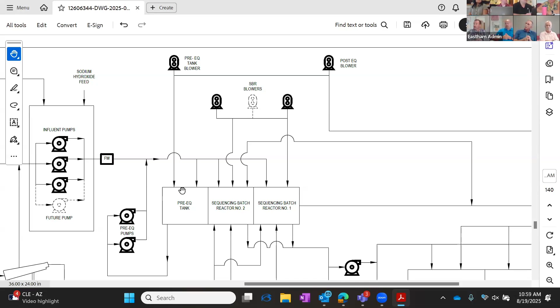The pre-equalization basin will also be there for if you need to take a basin out of service, so you can direct flow into the pre-equalization basin and get into the SBR to change out diffusers if needed.